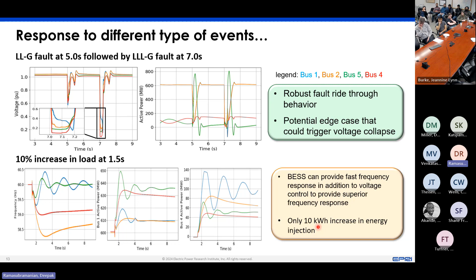If you want to look at it from a load increase perspective, we were able to see that you can go from a response that is something like this, wherein you have sluggish behavior, to something that can actually control frequency quite fast around the nominal value with very little change in energy injection. Actually, it was only around 10 kilowatt hours of increase in energy injection, which for these large batteries is pretty much nothing because they do have a much larger energy capacity. So going from a plant level slow sluggish response, taking it down to the inverter level, utilizing the fact that the inverter can actually provide that capability, does provide an improved benefit to the system. And that was on a microcosm system.